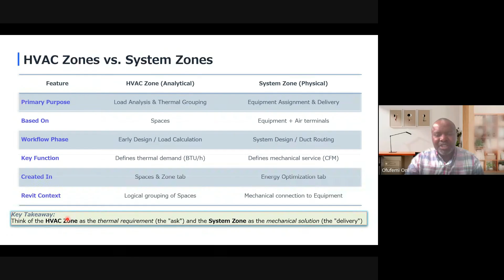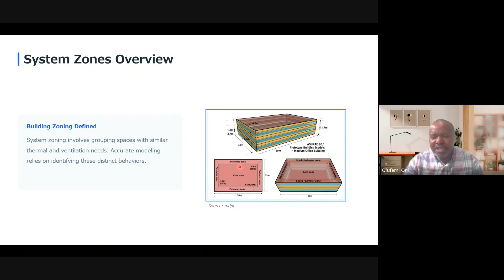To really understand what we mean by system zone or HVAC zone, let's look at this layout. We have a building where the perimeter zone is just corridor, but the building is wrapped in glazing, and the core zone is filled with office desks, occupancy, equipment, and so on. This corridor has no occupancy, but there is so much solar load from the environment into this space, so the heat gain here will be due to solar gain and conduction. You need to cool this corridor.